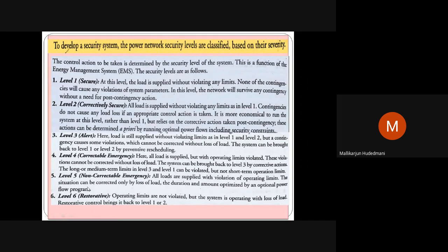So another state is level 5, non-correctable emergency. Look at the information. All loads are supplied with violation of operating limits. Most of the components are on the verge of tripping. They are violated. Surely at any moment they may collapse or fail. The situation can be corrected only by loss of load. There is no other solution. The only solution is to reduce the load, remove the load itself. The duration and amount are optimized by an optimal power flow program. You can calculate this; the non-correctable emergency has really set in. Every component is really out of your control. The moment the next change in load is noticed, the system is sure to collapse. In that situation, your computational algorithms help you. The optimal algorithm is supposed to get you back to at least a controllable state.